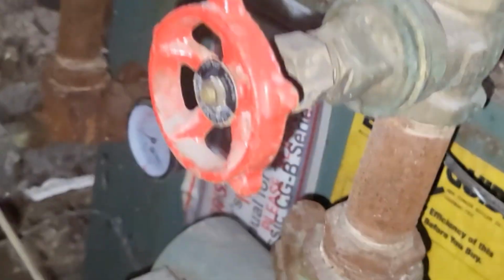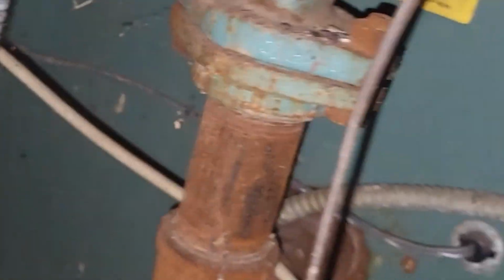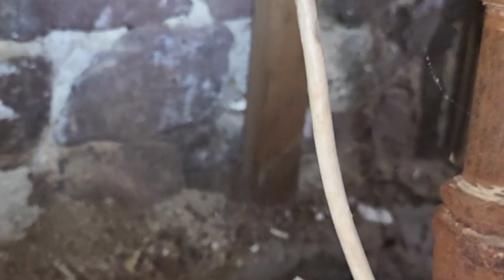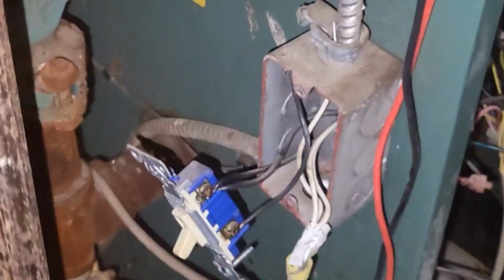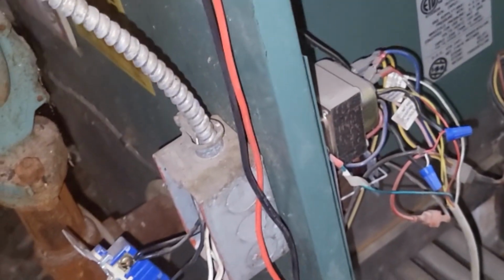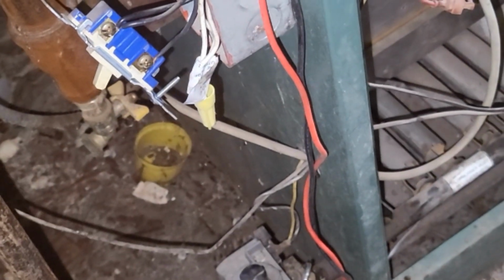since we know what side of the pendulum we're dealing with, a 115 volt issue can cause the breakers to trip. I'm just looking at all my wires. Everything was good inside my switch. We got a damper, which is 24 volts. Should be a 24 volt low water cutoff. I'm just looking for any obvious signs of any cross wires or any burnt wires, but according to this landlord, everything's been working up until a few days ago. What I don't know is if they had something plugged in upstairs that could have overloaded this circuit.